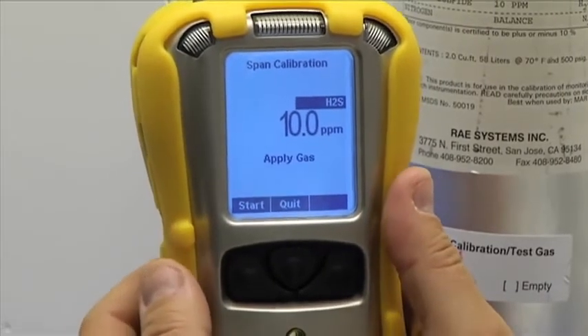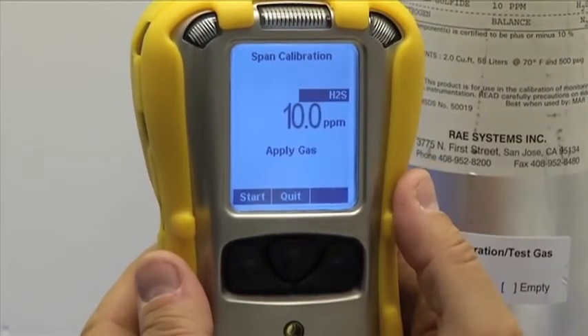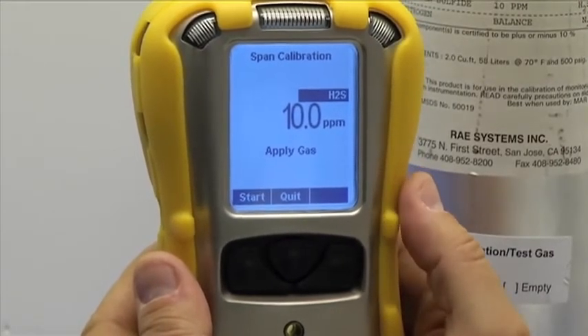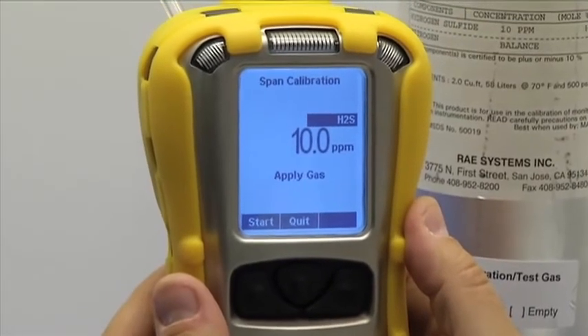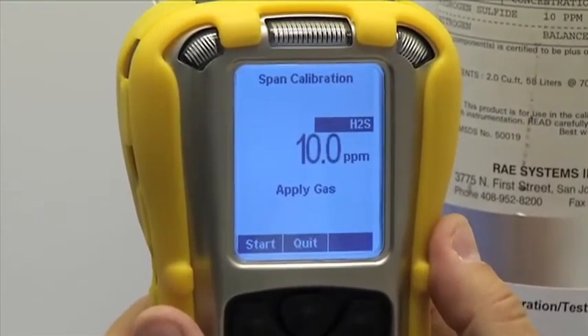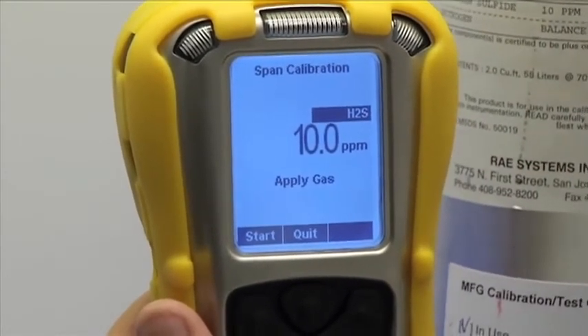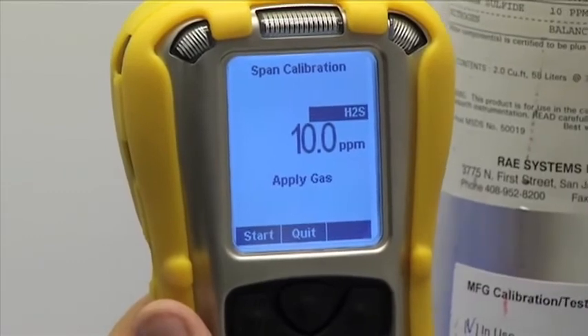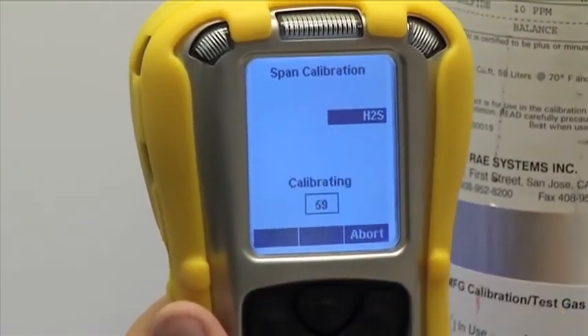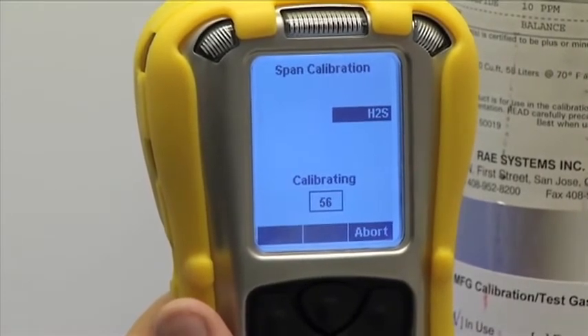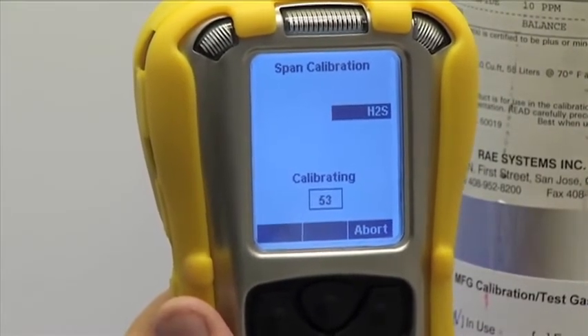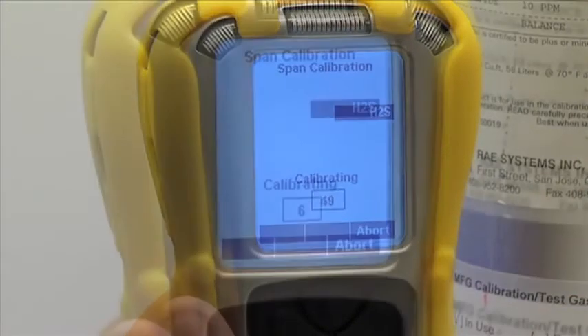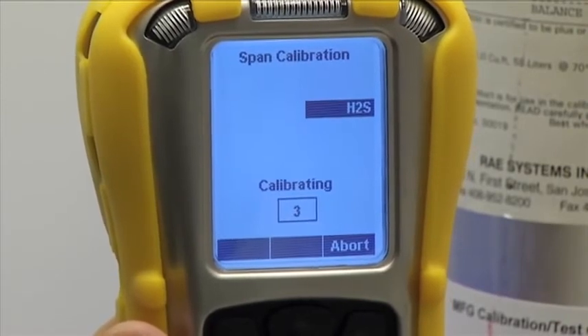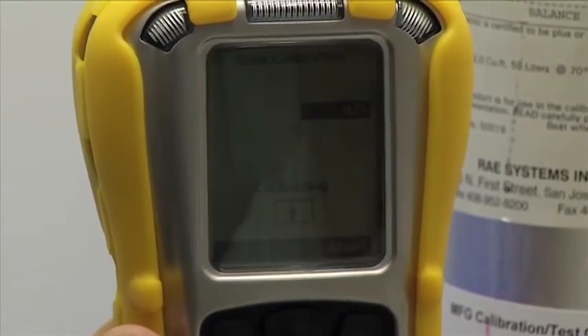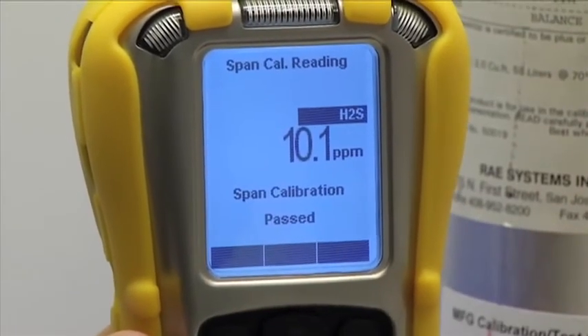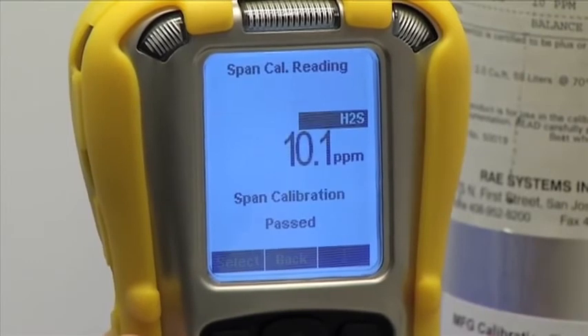This screen tells me the information about the span calibration for the H2S sensor. It's asking for 10 ppm H2S as the default calibration gas concentration. That's exactly the concentration written on the cylinder that I've connected my instrument to. So we'll start the gas flow and press the Start button to start the calibration. A 60-second countdown begins. I can abort the calibration process at any time by pressing the Abort button. When the calibration completes, the instrument produces a screen with the calibration results in a pass-fail format and the sensor reading at calibration value. So this sensor passed the calibration.